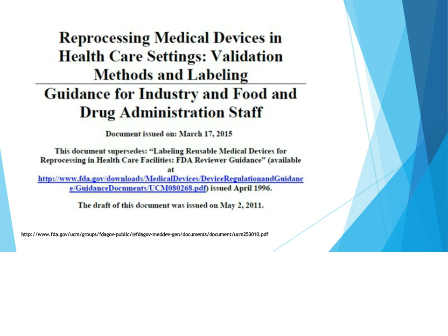Manufacturers should also design their reusable devices with an eye for effective cleaning. The 4 reprocessing situations listed here are covered in the guidance document. They include reusable medical devices that are either supplied sterile or non-sterile and are processed or reprocessed prior to use. Reprocessed devices that are reused only by a single patient, or single-use devices that are supplied non-sterile and require reprocessing or processing before use.